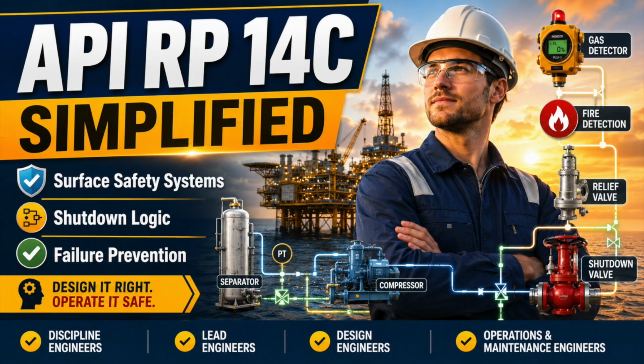Pumps and compressors must be analyzed by what they can physically generate. A positive displacement pump can continue increasing pressure against a blocked discharge until something fails. A centrifugal pump has limited shutoff head, but maximum discharge pressure must include maximum suction pressure, speed, and fluid density. A compressor package is not one black box. Suction, discharge, coolers, scrubbers, fuel, driver, enclosure, blowdown, and associated vessels each have distinct hazards. Package vendor protection does not remove the facility engineer's responsibility to integrate the package into the plant shutdown and relief philosophy.